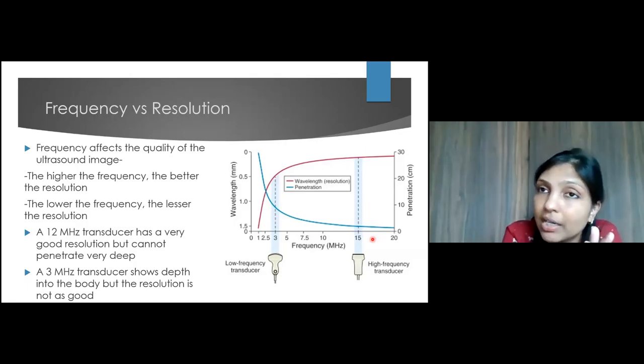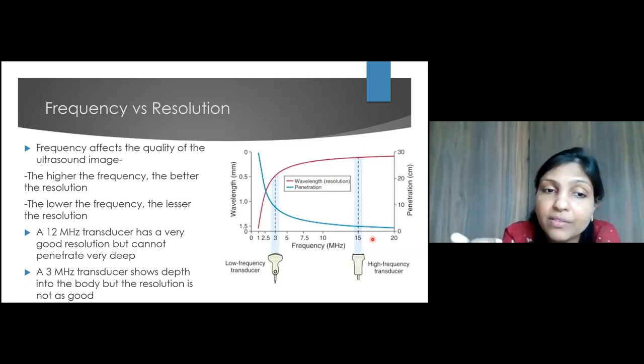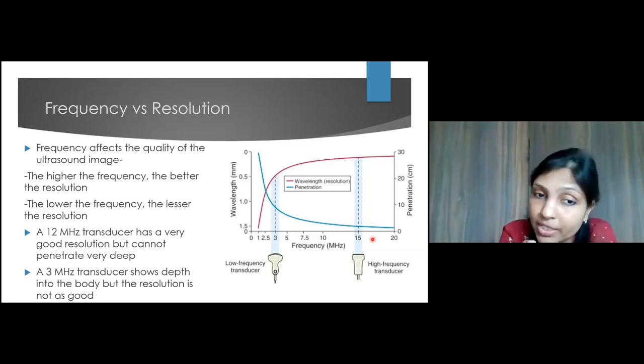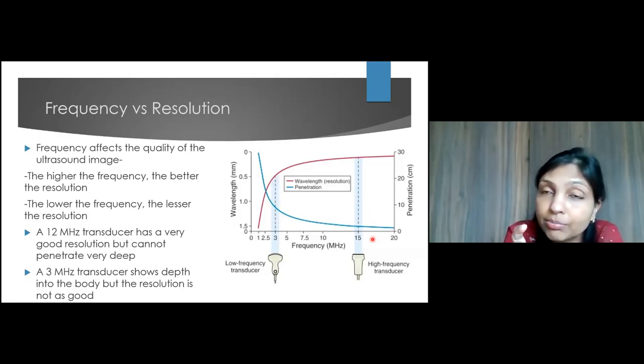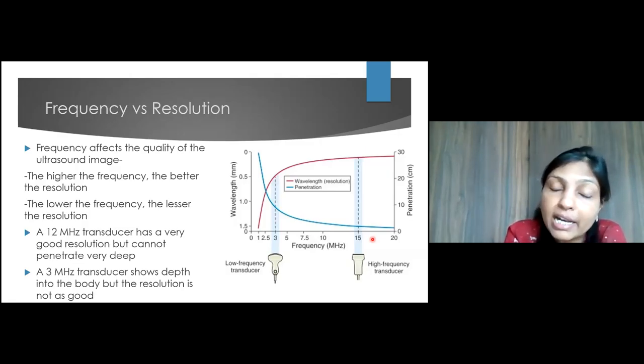You can see the superficial structures very nicely, but it may not be able to capture very deep images. So it cannot penetrate very deep. Whereas if you have a 3 megahertz transducer, which is a lower frequency, the resolution may not be as clear, but it can travel great depths. So we utilize this when we are looking for structures which are deeper to the skin.